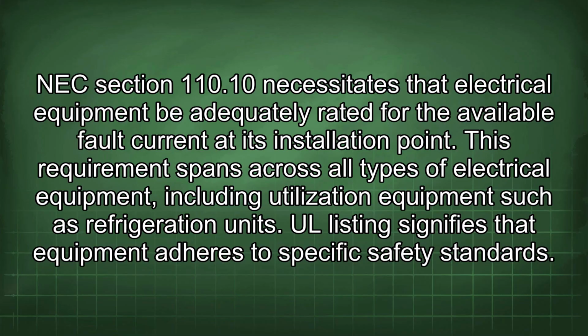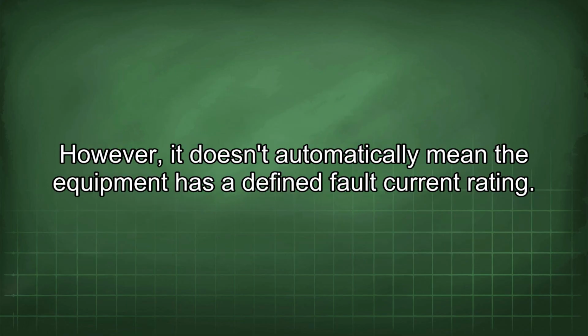NEC Section 110.10 necessitates that electrical equipment be adequately rated for the available fault current at its installation point. This requirement spans across all types of electrical equipment, including utilization equipment such as refrigeration units. UL listing signifies that equipment adheres to specific safety standards. However, it doesn't automatically mean the equipment has a defined fault current rating.